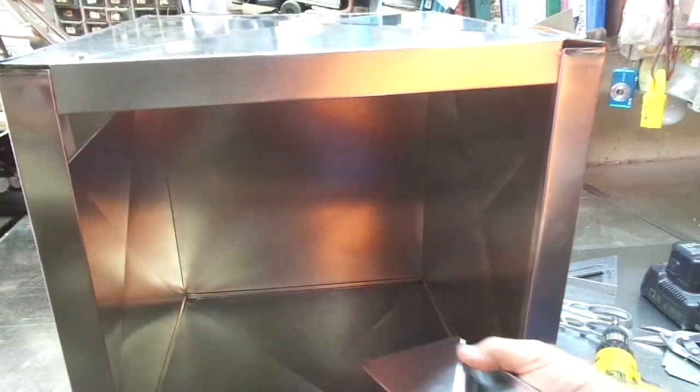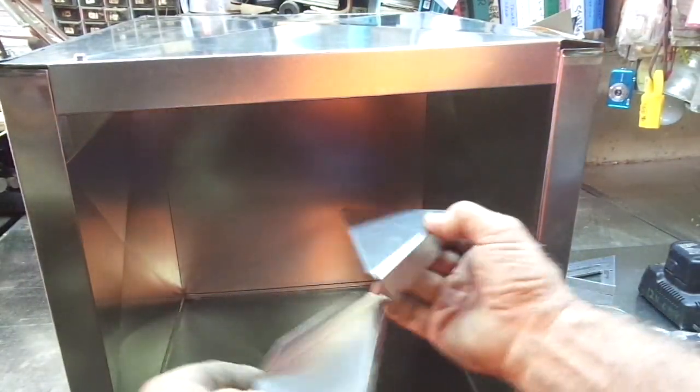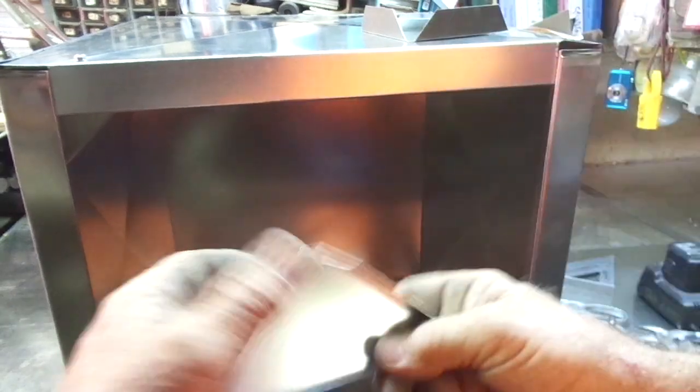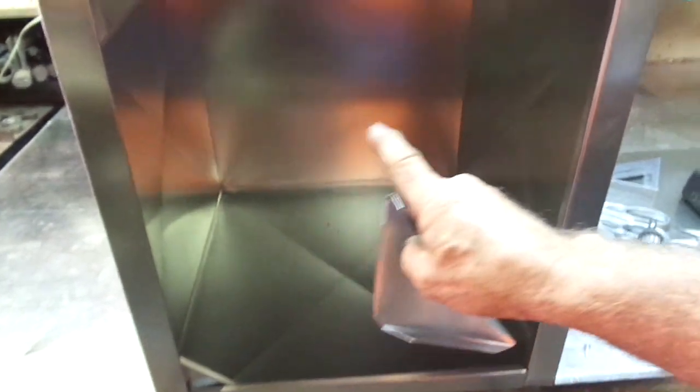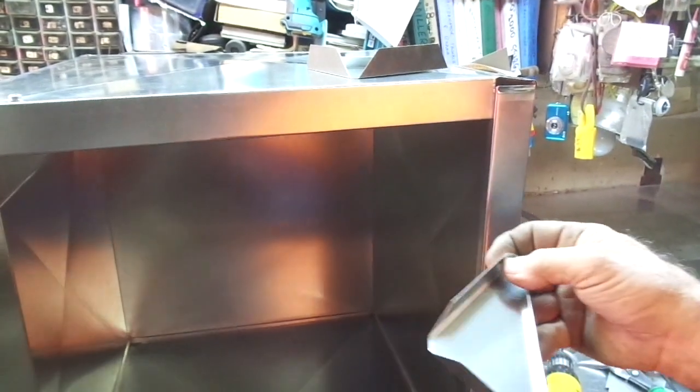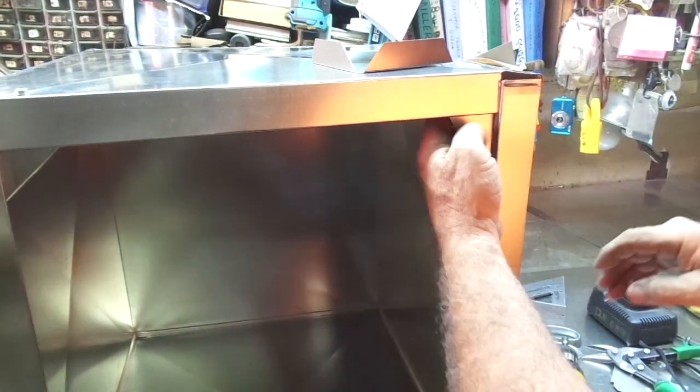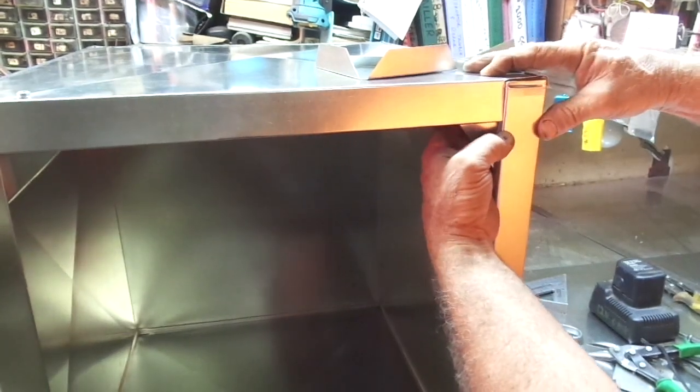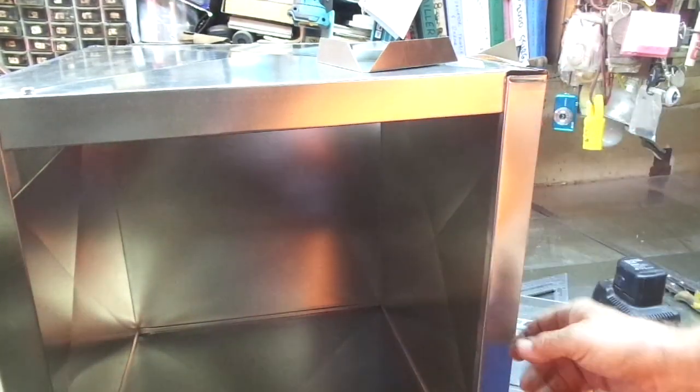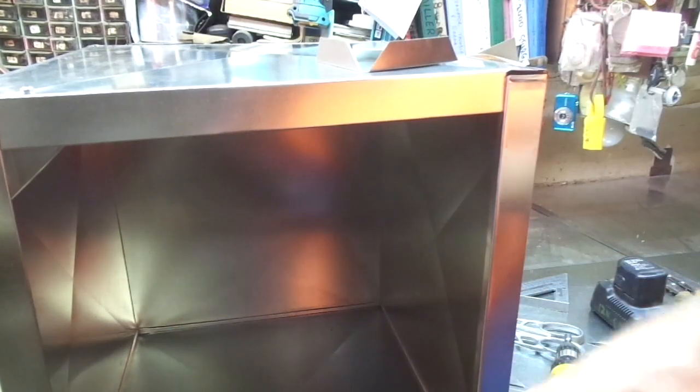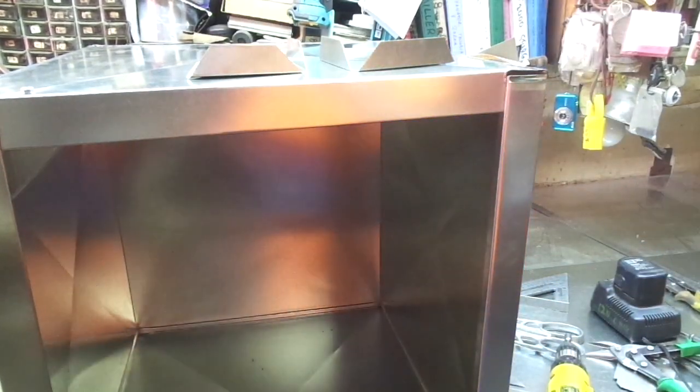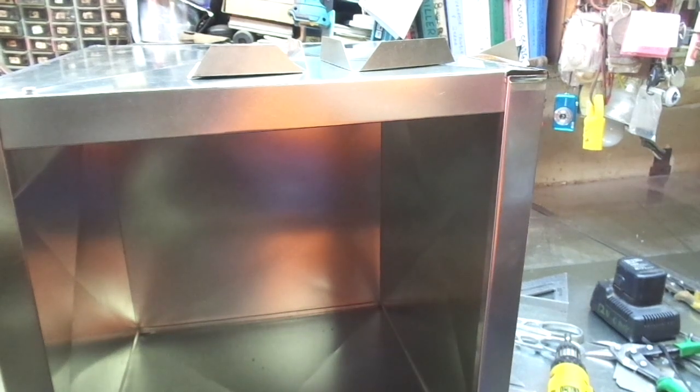Now we're going to do the same thing on this other side. Height-wise, everything is fairly tolerable. It's all adjustable. You can take a tri-square and just lay out some scrap 90s out of your scrap pile that you just created whenever you made your plenum. And you're going to go ahead and notch these guys all around. And we're going to fold these into 90s and then give that a little reinforcing edge. I'm going to show you how to even more securely stabilize the corners of a plenum box. Here we have the four little angles laid out, folded. You can see two of them are installed in this corner and in that corner.